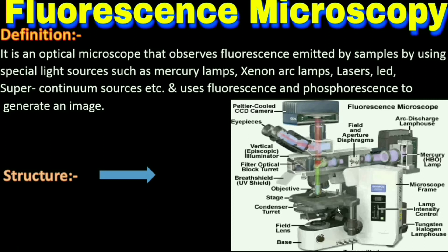After the sample, when illumination starts, emission starts from the specimen. This emitted light reaches back to the objective lens, passes through the objective lens, reaches the dichroic mirror, then after the dichroic mirror it reaches the emission filter, and after that it reaches the detector.